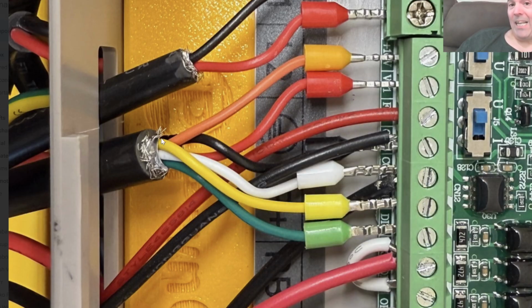Now, a shield drain may sneak back a little bit on one end or the other. It's just depending on tension. I see that done all the time. When I say a little bit, I'm talking maybe 3 millimeters, 4 millimeters.